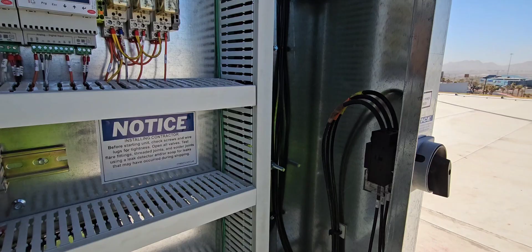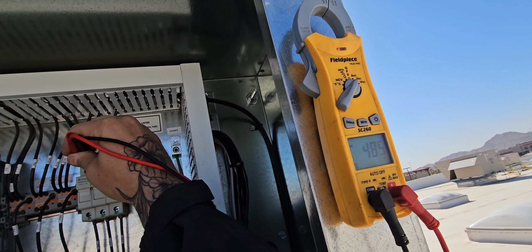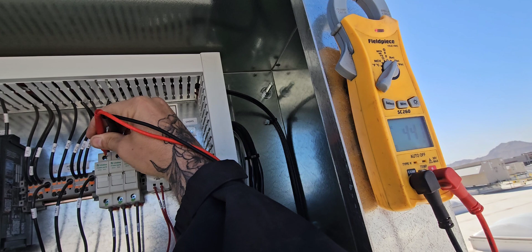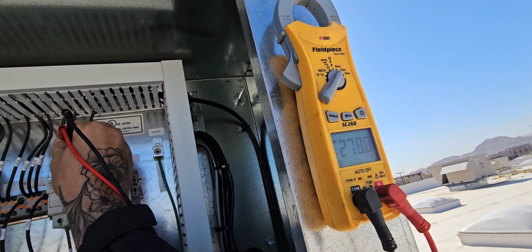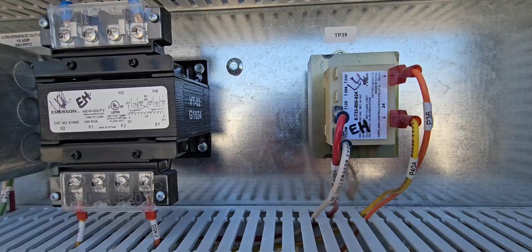So what I'm gonna do now is start checking my power, make sure I've got 460 coming in. Let's see, put that right there. So let's check the top of this. That's 2 to 3, and then 1 to 3. Okay, and then I'll check all of those to ground, make sure I've got a balanced load on this thing. 280, 278, 280, okay.